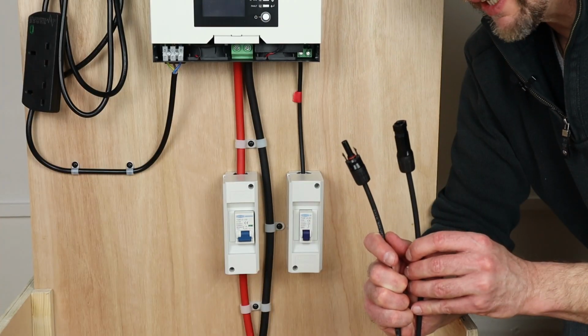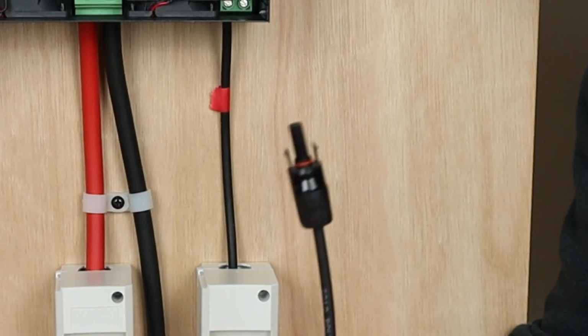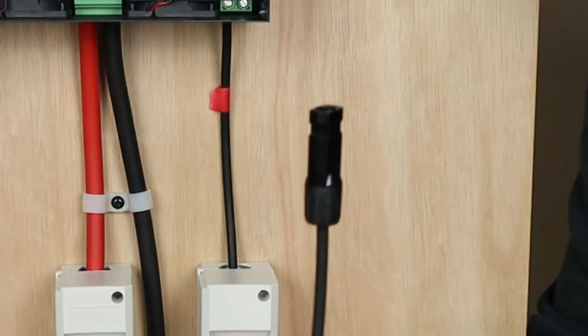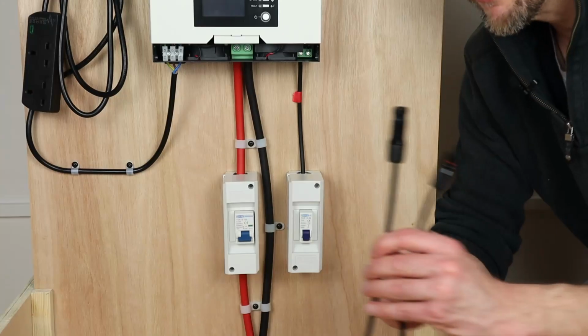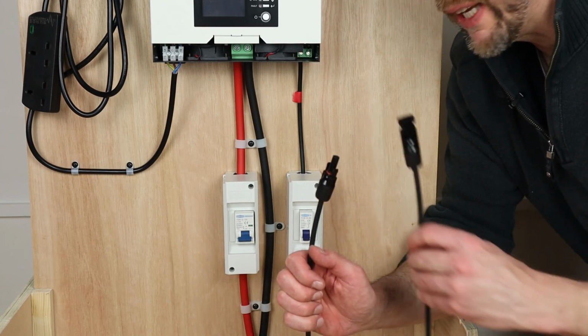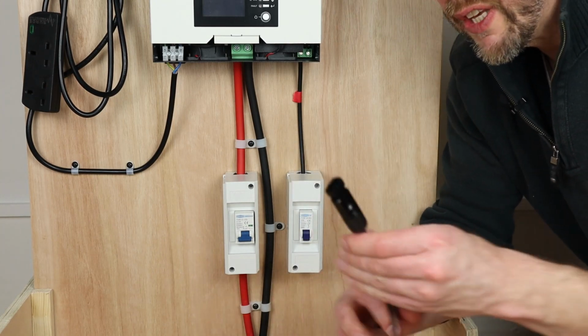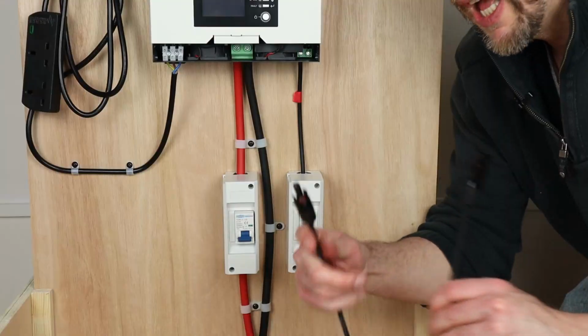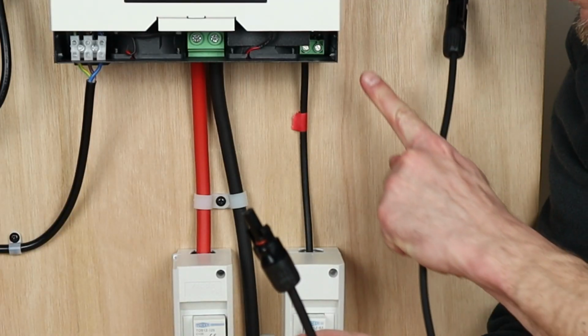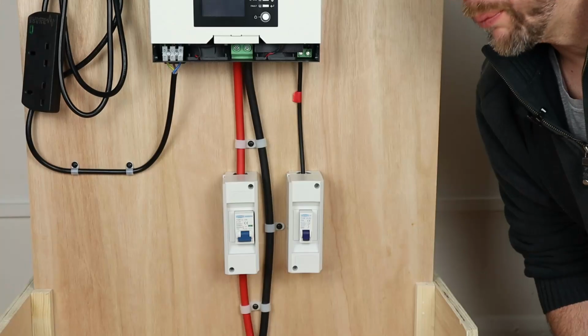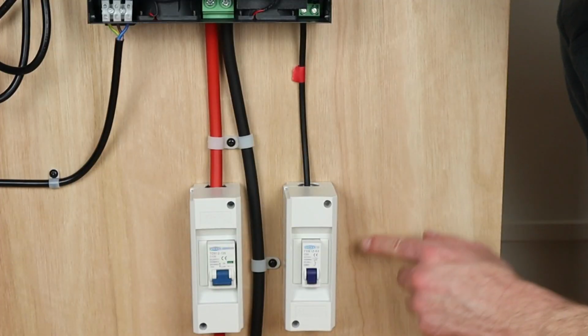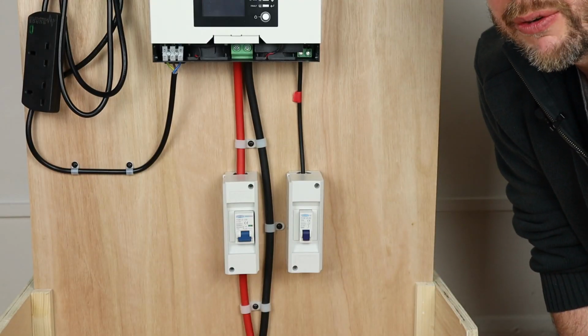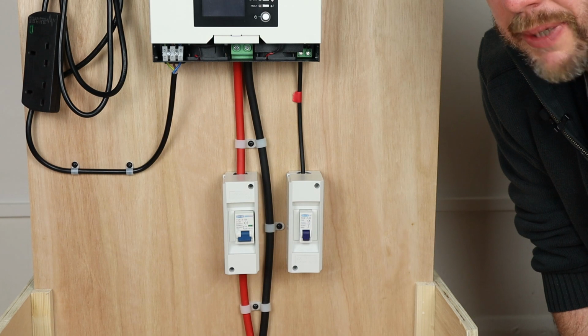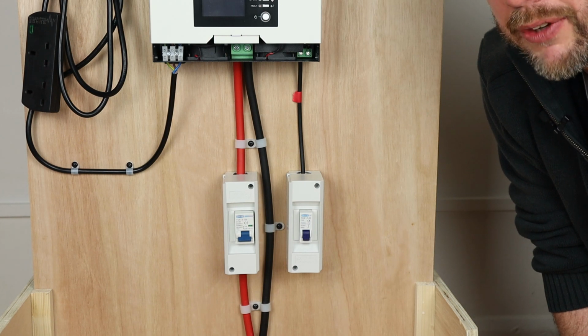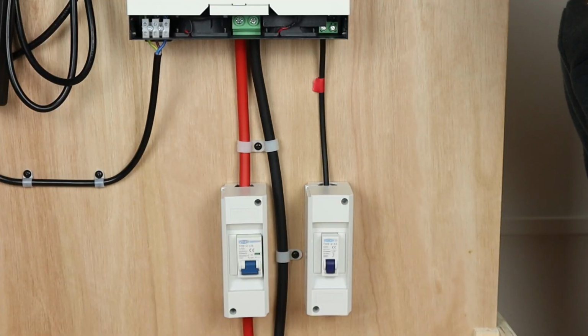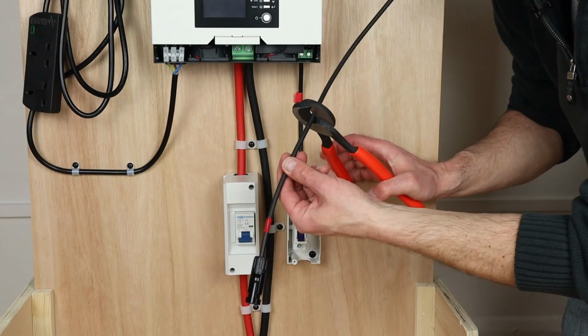Usually when you connect up to solar panels, this MC4 connector from the panel is positive and this one is negative. So to connect to this breaker, we need to turn them around: this one now becomes the positive and this becomes the negative, connecting to the other terminal up here. But before connecting solar panels directly to it, we're going to check with the multimeter to make sure the polarity is the right way round. I always recommend that, just in case you've got them wired the wrong way round.